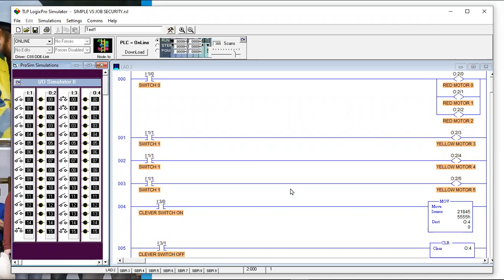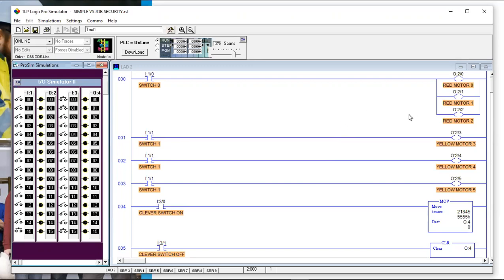If we needed to troubleshoot this — and that's what it's all about, one big reason to keep it simple — let's say somebody says red motor one is not running. We could look in the schematics and see that red motor one is output two-one. We can go look at the indicator light on the card to see if that output is lit. We could also search for it in the logic — and even in a program with a thousand rungs, a search will show us everywhere that address occurs in half a second.